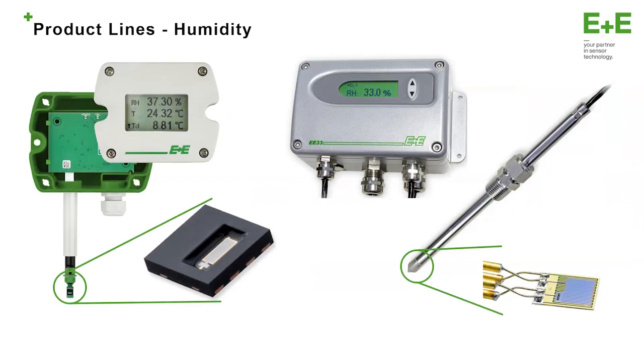And we can also add on the temperature sensor portion, which is shown right here as the smaller element itself. We can also transmit these values over communication technologies like Modbus over an RS-485 channel, Ethernet in some cases, but also analog channels, both 4 to 20 milliamp and 0 to 10 volts. So we meet all industry standards in that respect, and for any type of device this is going to be plugged into. That's on the more polycarbonate side, the HVAC side.